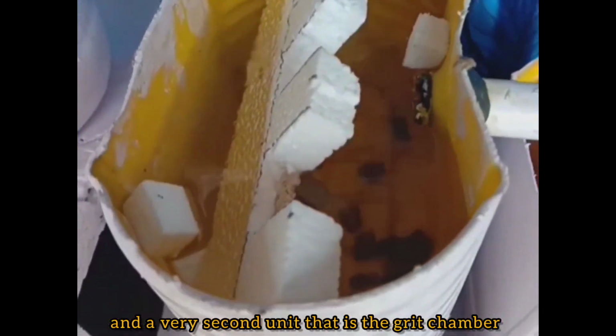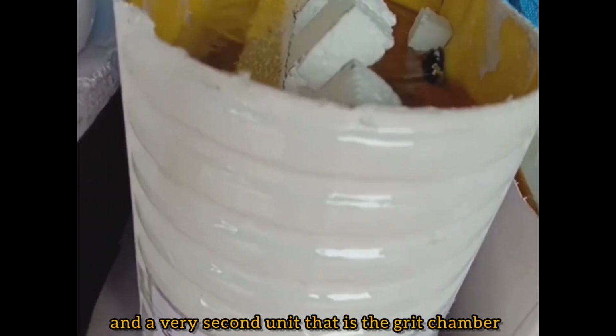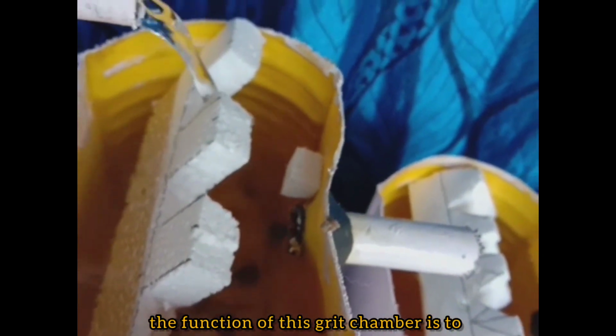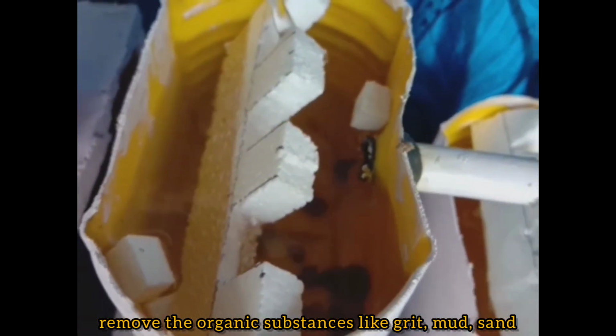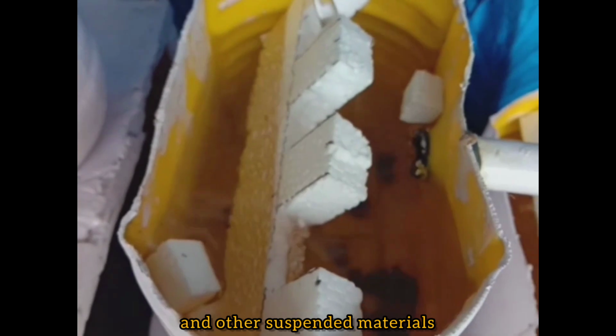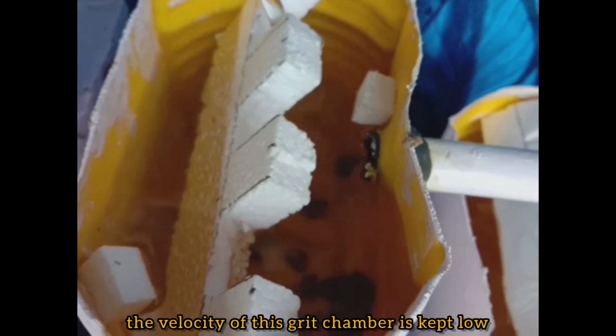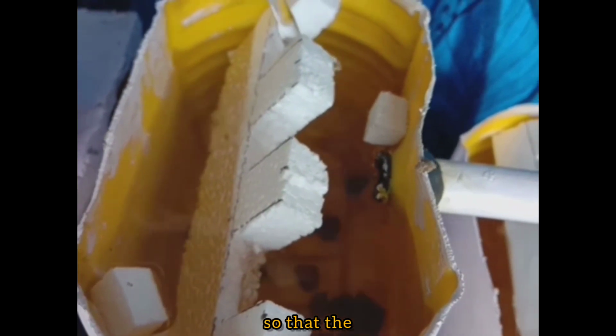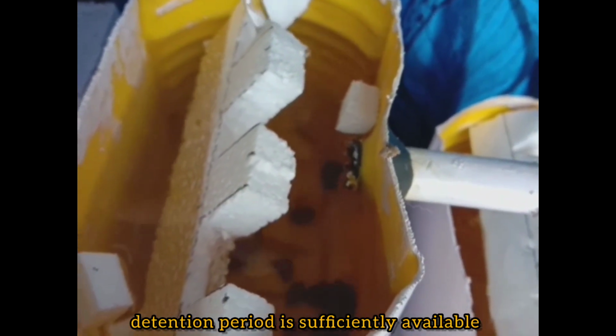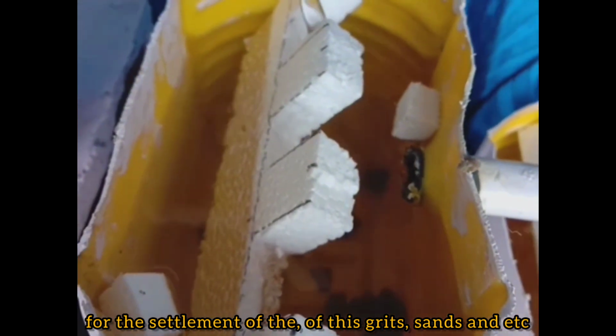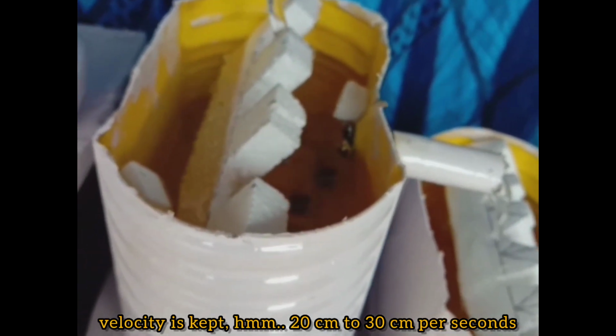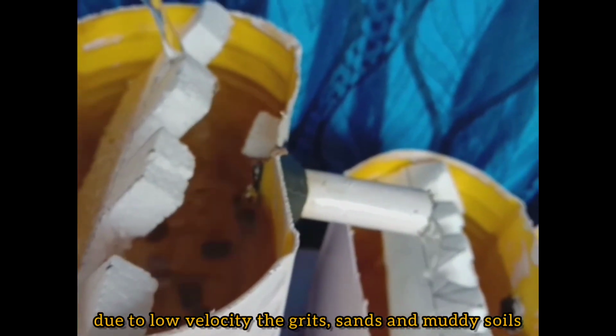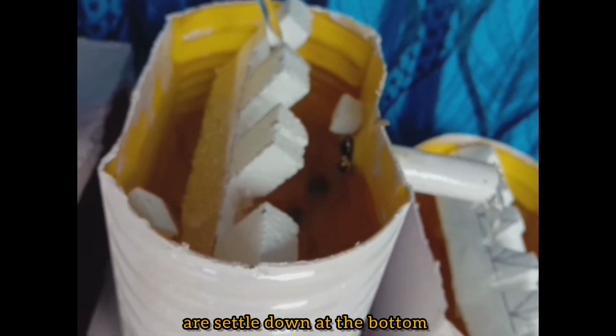And the second unit, that is the grit chamber. The function of this grit chamber is to remove inorganic substances like grit, mud, sand and other suspended materials. The velocity in this grit chamber is kept low so that the detention period is sufficient for the settlement of grit, sand and so on. Velocity is kept at 20 cm to 30 cm per second. Due to low velocity, the grit, sand and muddy soils settle down at the bottom of this grit chamber.